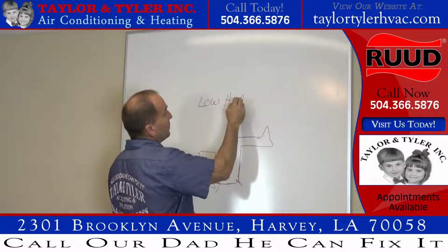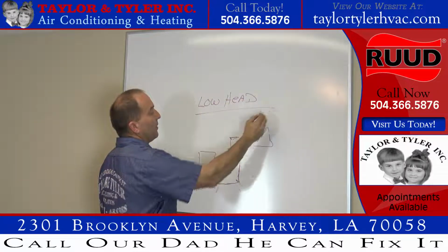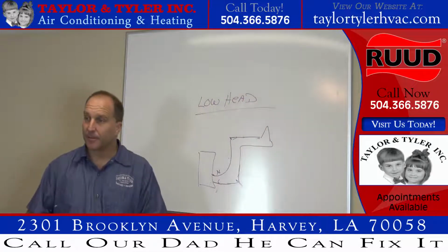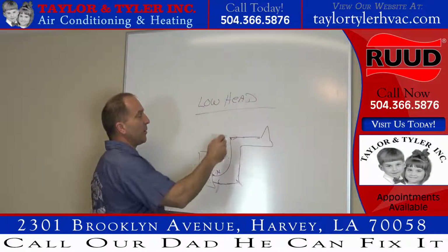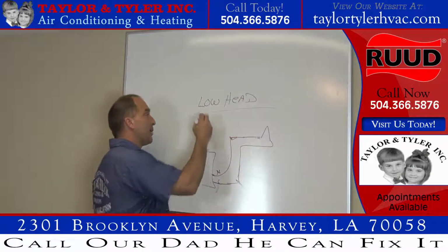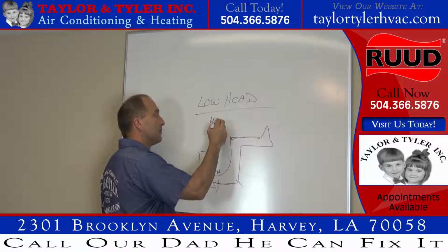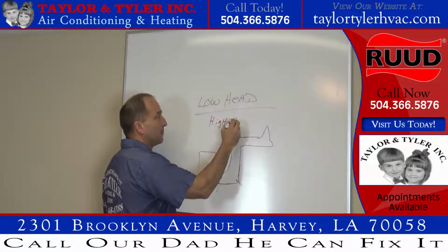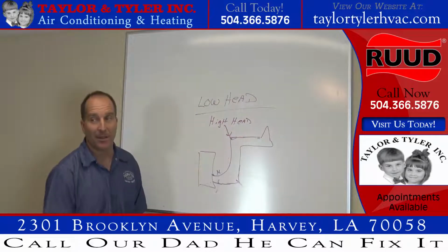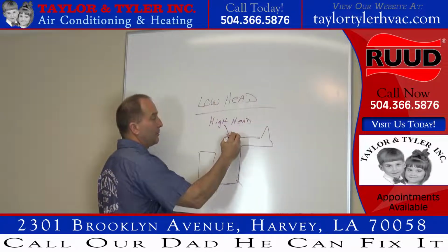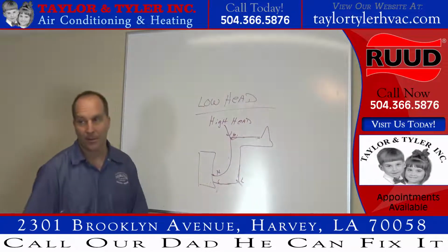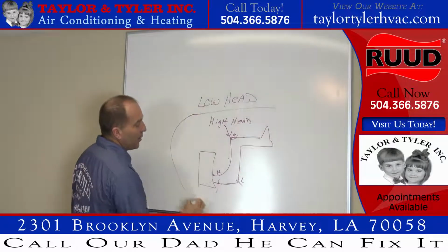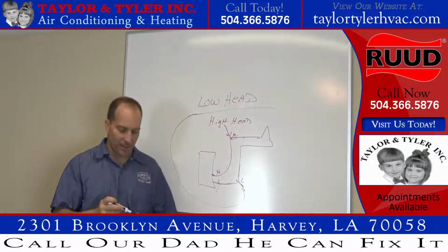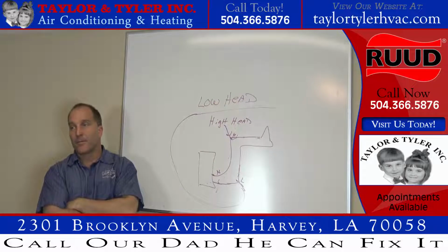Low head pressure. Now wait a minute, that doesn't make any sense, Eric. You told me right here, when this kink was here, I had a high head pressure, right? Boom. High head pressure here. That's on my liquid line, right? High side line. This is my low side line. Well, then this one's going to give me a low head pressure when my kink is in my suction line. Does that make any sense? I'm trying to wrap my head around it.